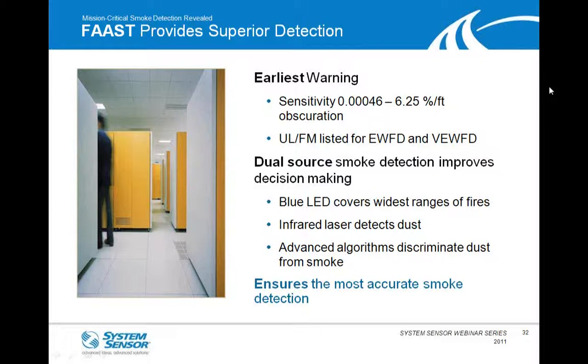And then what we do quite a bit differently from a lot of other aspiration systems is instead of having a single source looking for the incipient stage of a fire, we actually have 2 sources. So we're using a blue LED that covers the widest range of fires, especially in the incipient stage. And then we're using an infrared laser basically not to detect smoke but to detect dust.